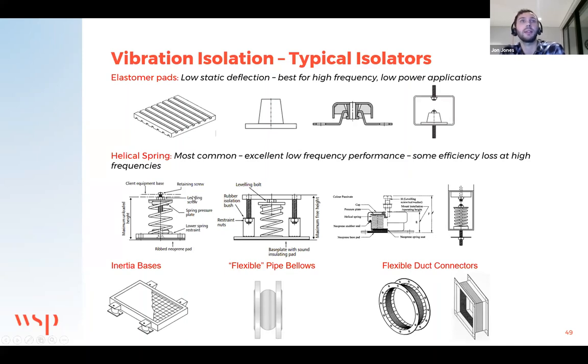To get the best out of a vibration isolator, the isolator needs to be loaded. And so we talk about the static displacement of a spring, for example, as a measure of its performance. Of course, the spring can't be designed to bottom out. If you put a very heavy weight on a spring, it's going to squash, it's going to bottom out, it's going to do nothing. So it needs to be designed such that, given the dynamic load and forces that it's going to be operating against, the greater the static deflection of the spring, the better the isolation efficiency. So that's what we're looking for essentially when selecting springs on equipment: to load them to the best possible place without bottoming them out.